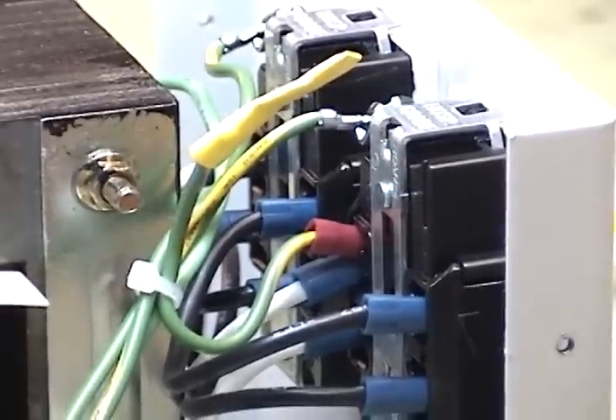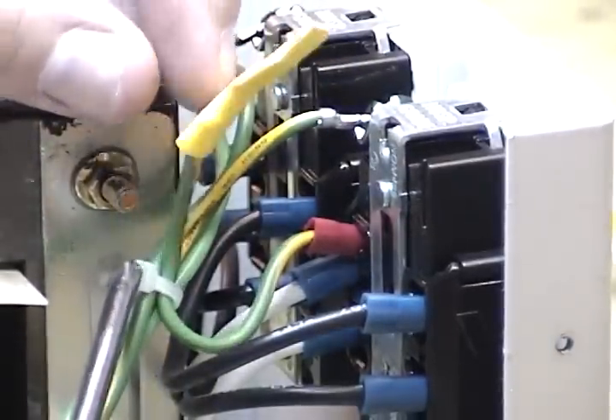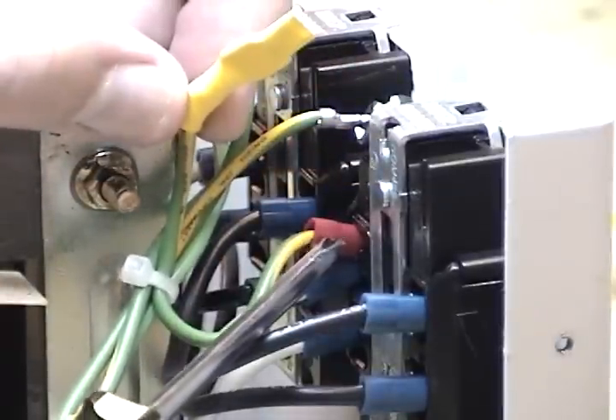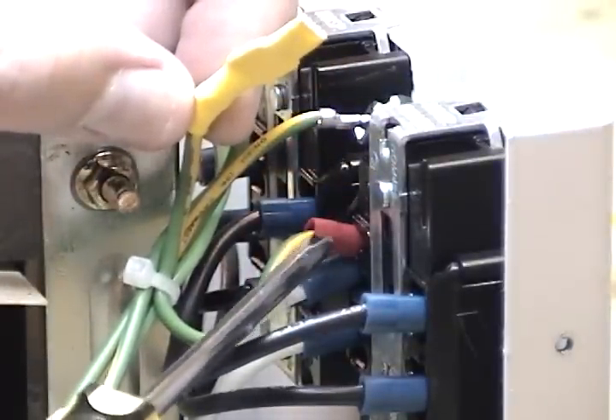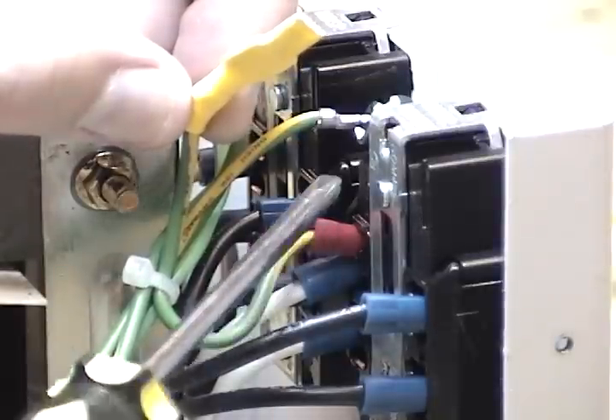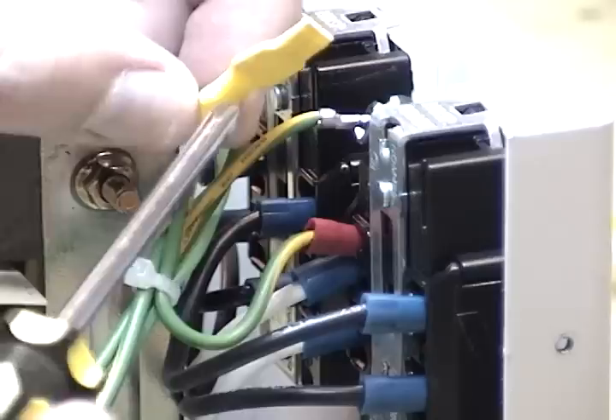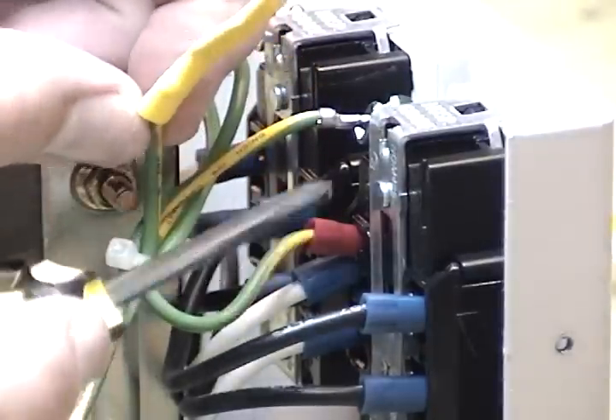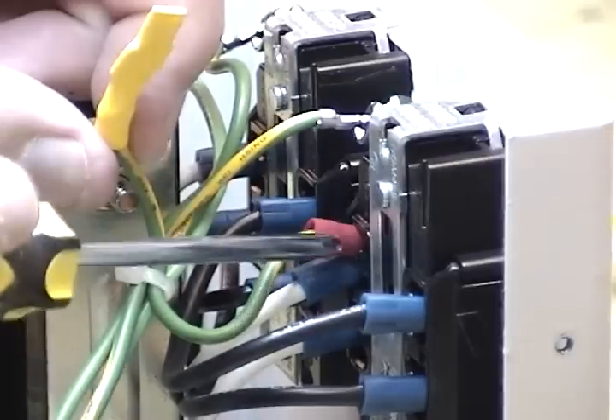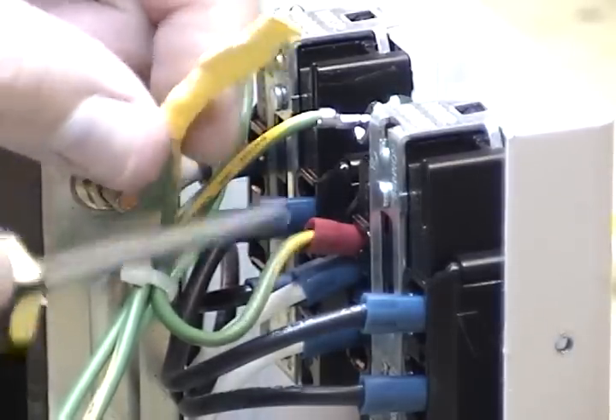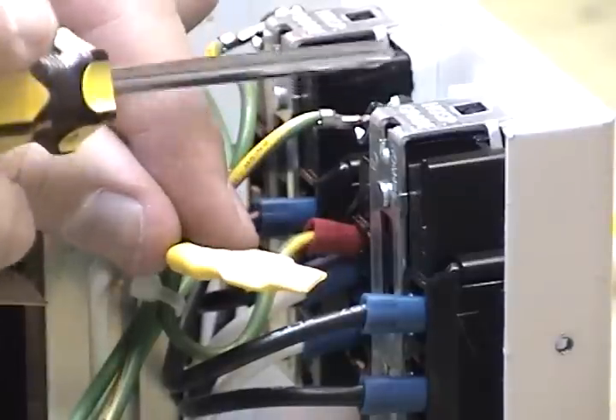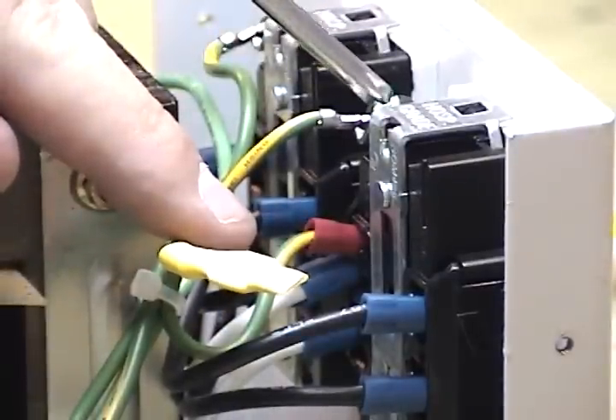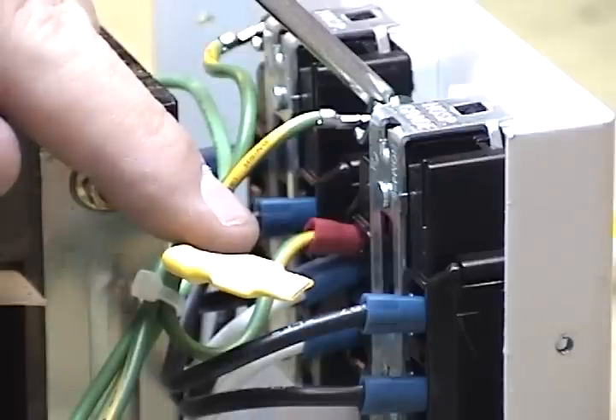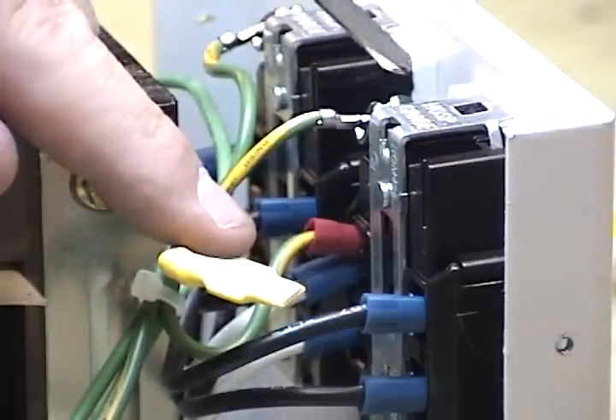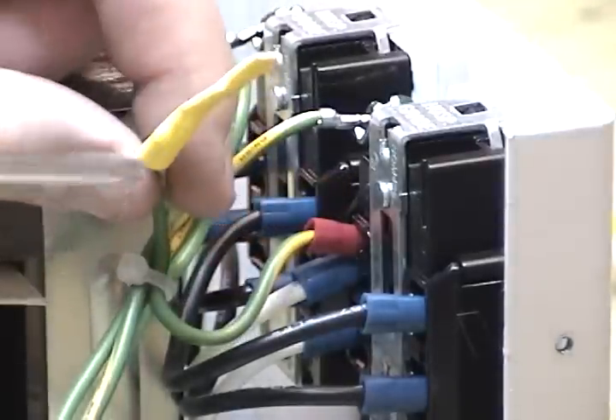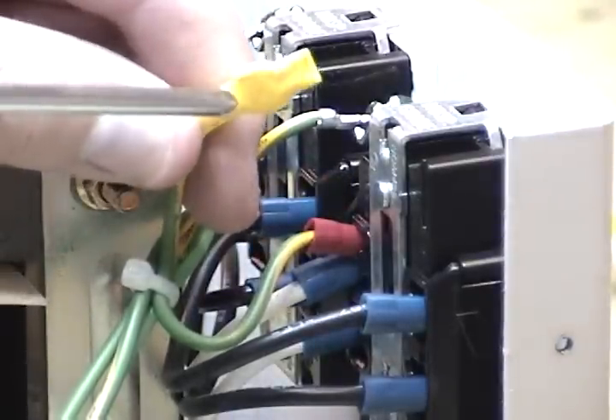This is that strap from the secondary that goes down to the common connect on this outlet and straps the secondary transformer windings to common, essentially strapping it to ground. I've taken that ground strap off, and rather than trying to get in there and take those protective shields off to unscrew that, I just left it connected there and unhooked it from up here at the terminal posts where these 3-prong grounding wires connect. I left them, of course - I only took off this one going to the secondary transformer coils.